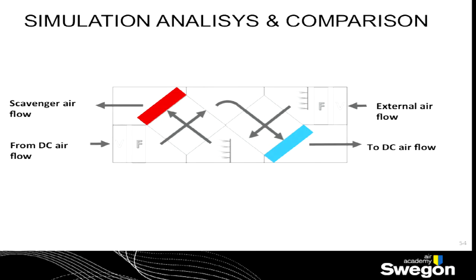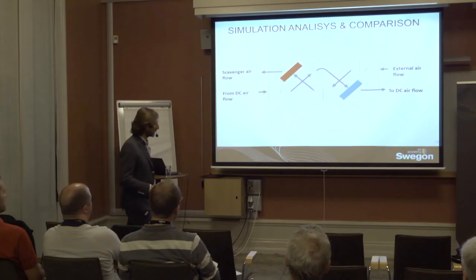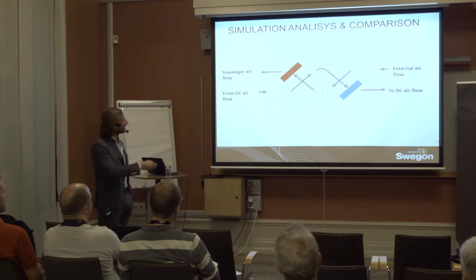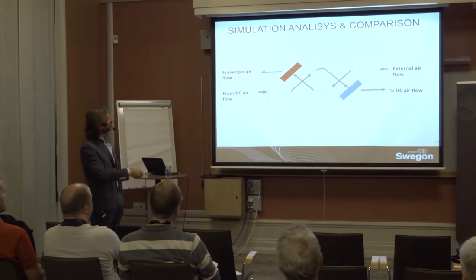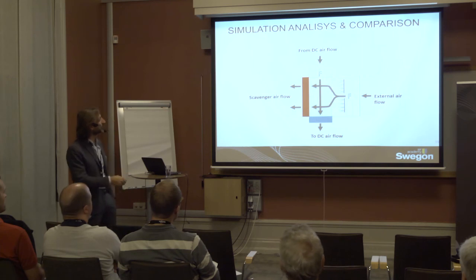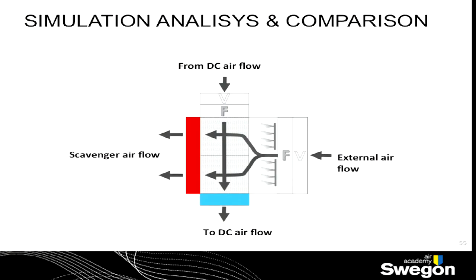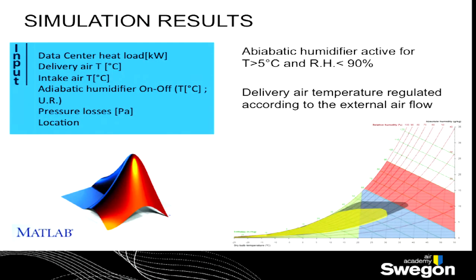Series to series plate heat exchangers. So both the air from the data center is crossing both of the exchangers, and the external air is doing just the same. Or a system like this one with a series to parallel flow, because the external flow is not crossing both in series, but only the air from the data center. We made just this kind of analysis just to have a complete overview of what is happening with this kind of system.